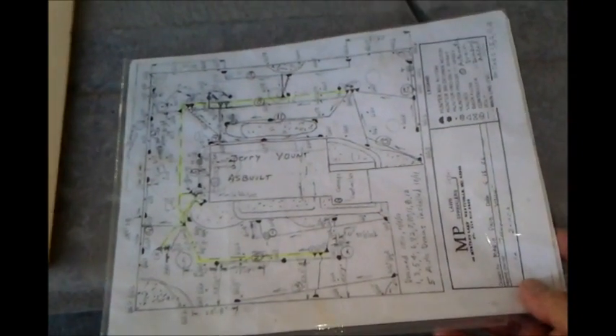So I'm trying to show you my as-built plan here. When the pressure is taken off of the sprinkler lines, the water in the sprinkler lines drains out through a drain that I've put on some of the branches, so you don't have to use compressed air to blow them out.